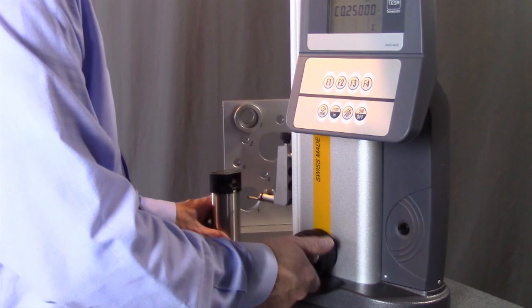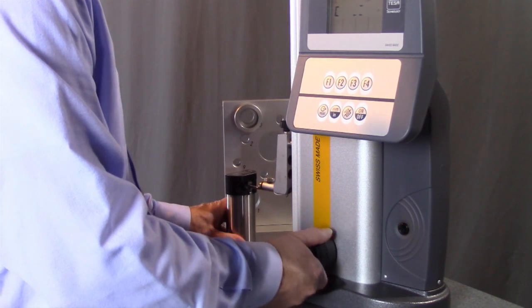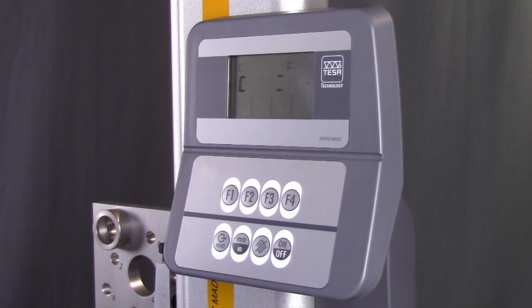It doesn't matter if you start by making contact on the top or the bottom, but you will take four hits with the probe on the setting master. When you're finished, the display reads start two and the gauge is ready to measure.